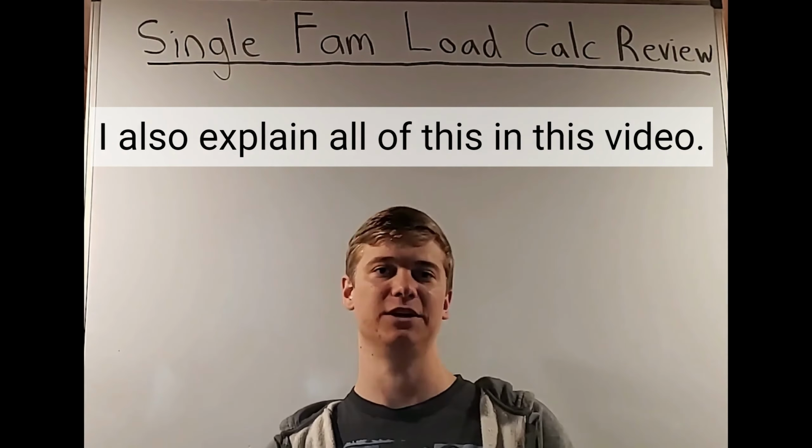And in that, I mentioned that's only in the standard method. So that's also what I'm going to highlight in this video. You'll see when I show you the page layout, along with the difference between the summary of each one, we're going to see that you do 25% of the largest motor for single family dwellings with the standard method, but for the optional method, you don't do 25% of the largest motor. That is just something you entirely do not do in the optional method. It's only in the standard method.